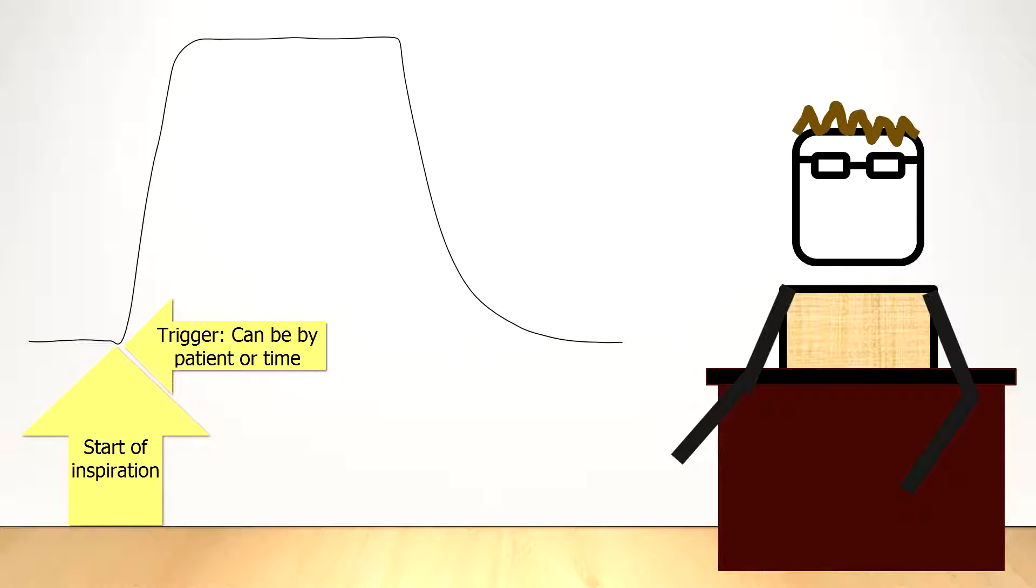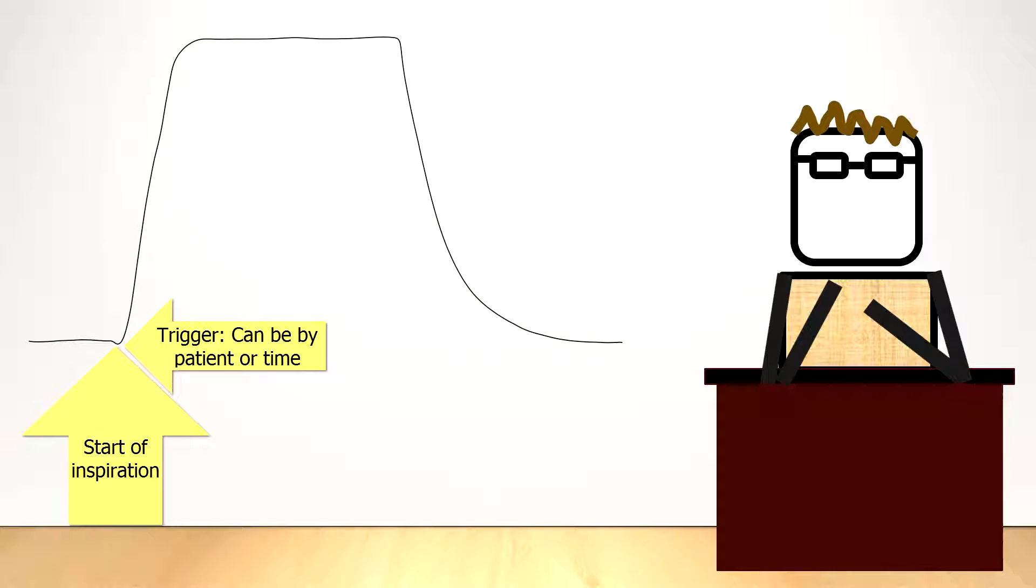One of two things can trigger the ventilator. Either the patient can request a breath, or a certain amount of time can elapse. The patient can trigger by starting to take a breath. The ventilator senses this and notices a drop in the pressure in the ventilator tubing, or that there's an increase in flow through the ventilator circuit. This is the clue to the ventilator to initiate the next breath.